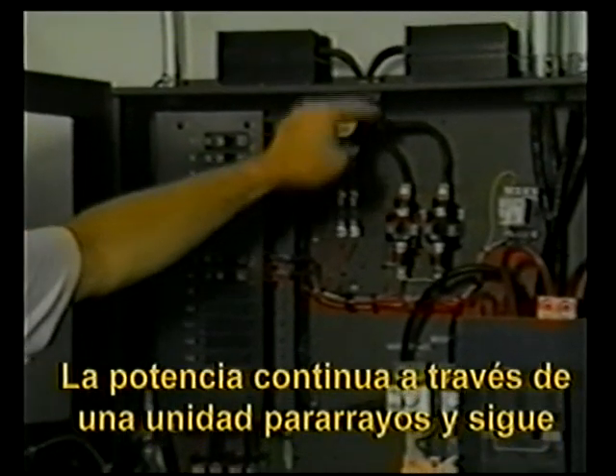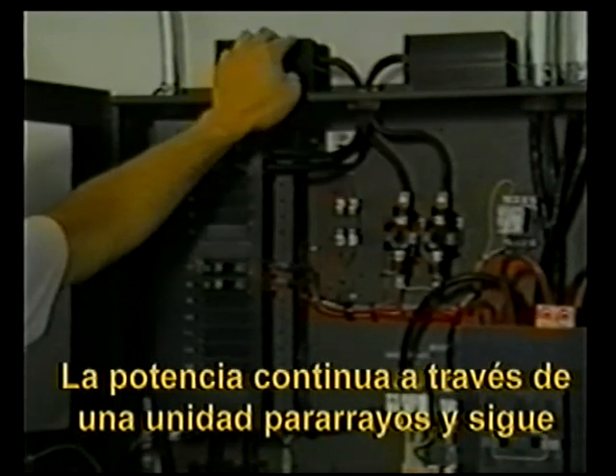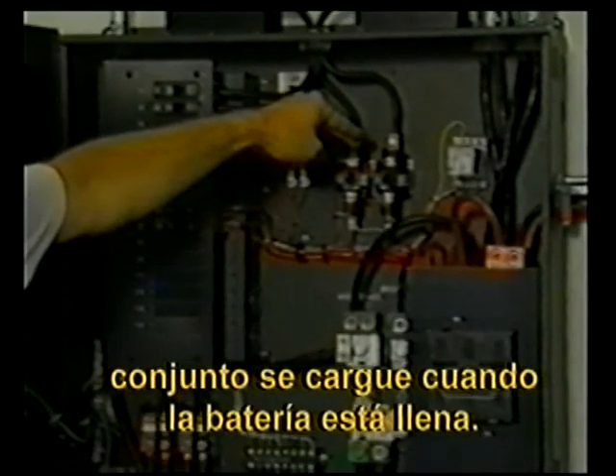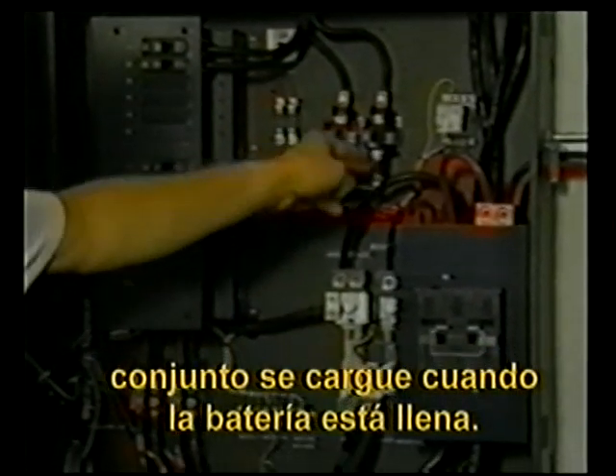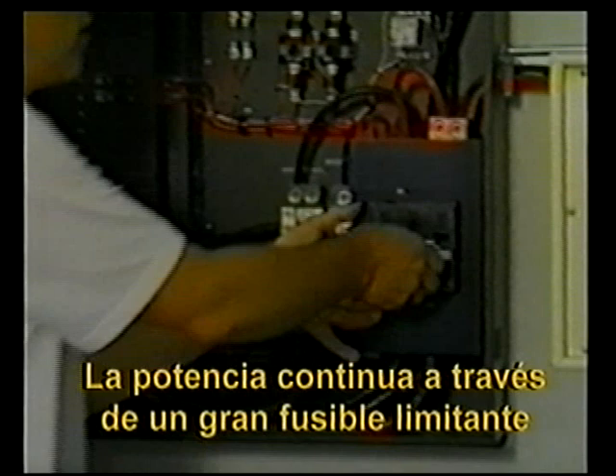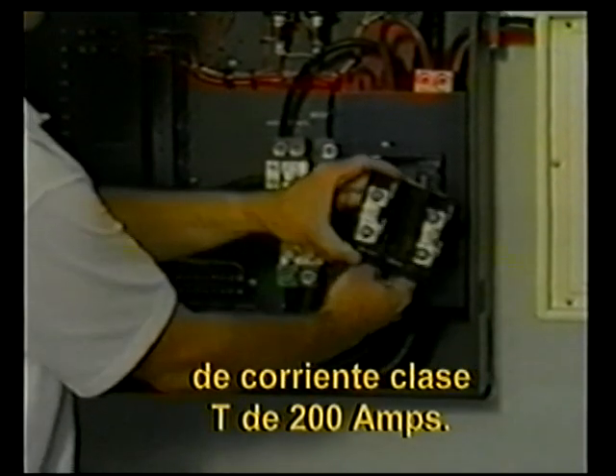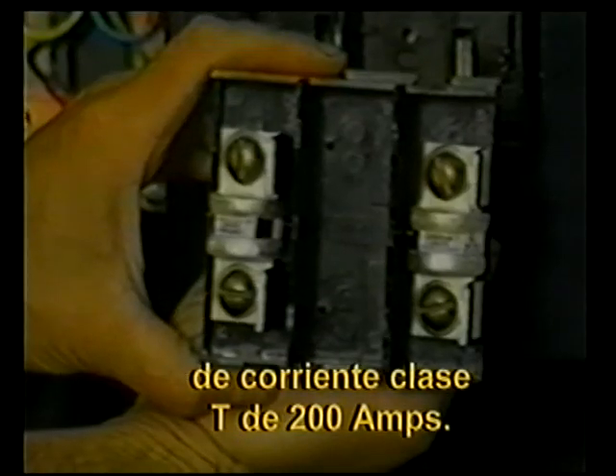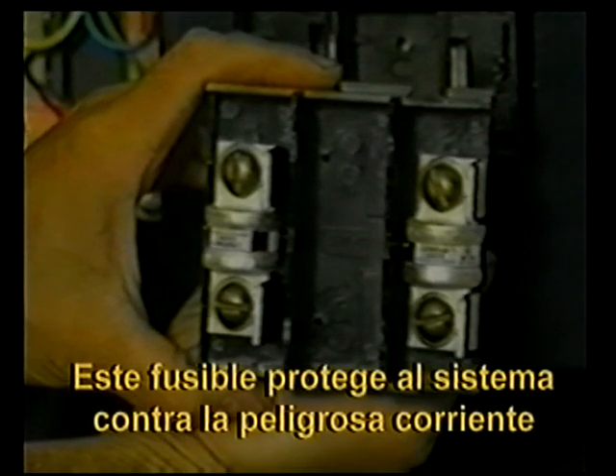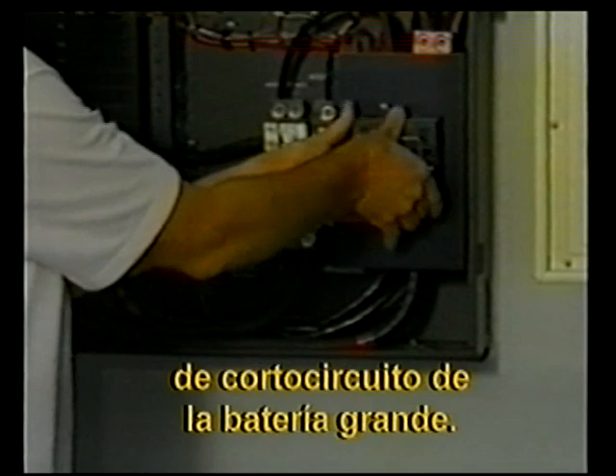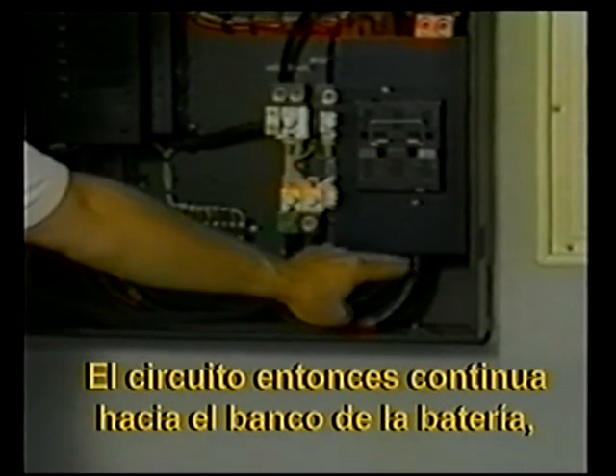The power continues through a lightning protection unit and then on to mercury switches that will stop array charging when the battery is full. The power continues through a large 200-amp Class T current-limiting fuse. The Class T fuse is chosen to protect the system from dangerous short-circuit current from the large battery. The circuit then continues onto the battery bank.